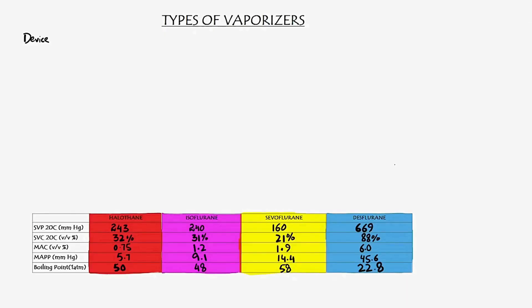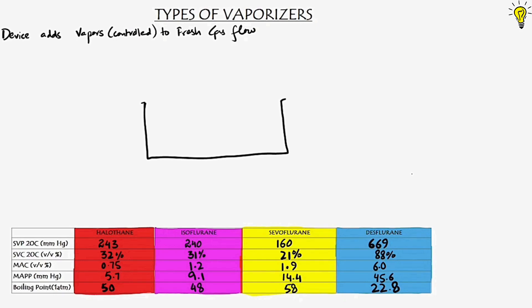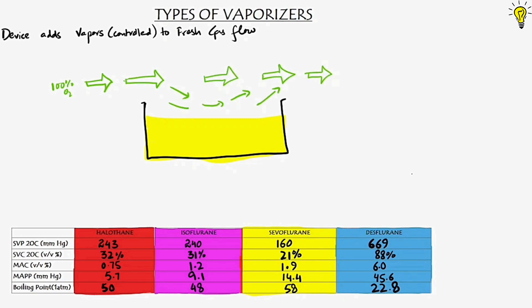So what are these vaporizers in an anesthesia machine? It is a device that adds a precise concentration of inhalational vapor into the fresh gas flow coming from the flow meters. This process can be accomplished in three ways. Number one: the flow-over system — oxygen flows over the vapor liquid chamber on its way towards the patient circuit.